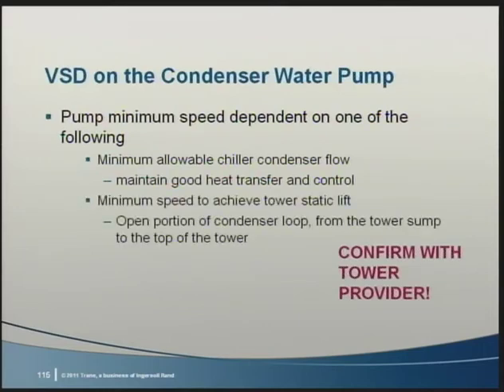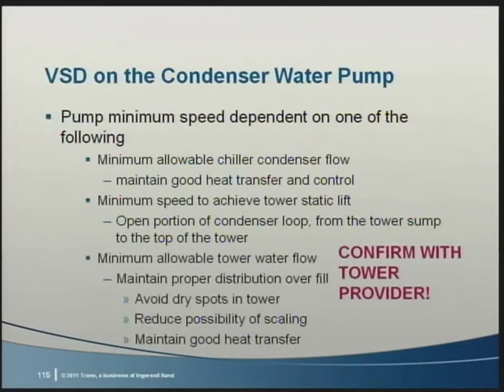The second isn't normally experienced but should be checked. Enough pressure must be developed to lift the water from the cooling tower sump to the top of the cooling tower, the open portion of the loop. If we reduce the condenser water pump speed too far, we'll get no flow over the tower. And we just discussed tower issues concerned if the flow is too low. Remember, there's always a minimum. With that preface, let's look at system operation when condenser flow is reduced.